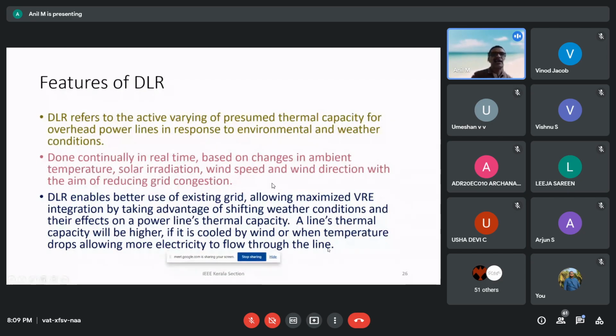Features of DLR. DLR refers to the active varying of presumed thermal capacity for overhead power lines in response to environmental and weather conditions. That is, the static line rating is decided by the temperature rise in the conductor and the thermal overload limit of the particular conductor. When the wind blows, or when the ambient temperature comes down, the temperature produced by the heating effect of the current flow in the conductor is cooled by the wind or low ambient temperature. So that climatic condition can be utilized to increase the load of the line, thereby deferring a capacity addition. That is the essence of DLR.